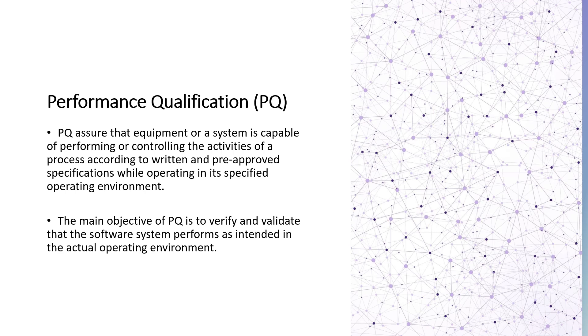The system performance is based on the respective operating procedure. For example, if you are having a chromatographic system, then you require an instrument method, a processing method, and a sequence preparation. So the system shall be performed based on the actual routine requirement, and in the performance qualification, we need to verify these things.